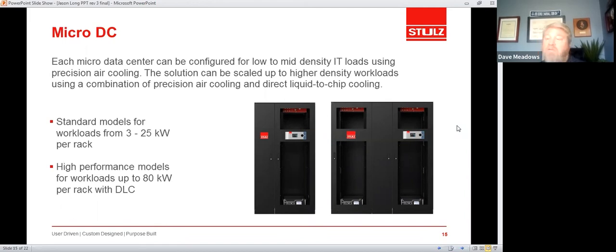So in these boxes, you can put them in places that are not quite as, say, pristine as a traditional data center. You can put it on a production floor, for example, to control CNC manufacturing processes. And the standard models basically are designed up to 25 kW of air cooling. Now, we do have some cutting edge technology that we can apply for much higher loads, up to 80 kW.